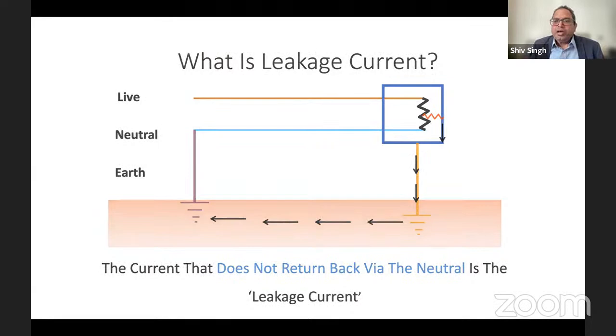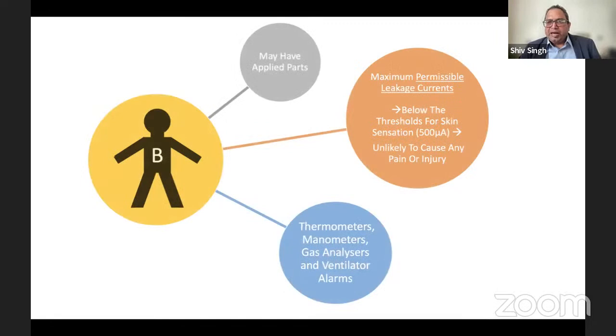So we look at how the equipment is classified based on the allowable leakage current. If you see a symbol of a man, only a man, not inside a box, that is type B, B for body, you can remember it that way. Now this can be applied to the patient, but the maximum permissible leakage current is below the threshold for skin sensation, that is, less than 500 microamps. You need at least 1 milliamp to feel the tingling sensation. 5 milliamps will cause pain. 15 milliamps will cause muscle spasm. So this is below the threshold for even sensation, and is unlikely to cause any pain or injury.